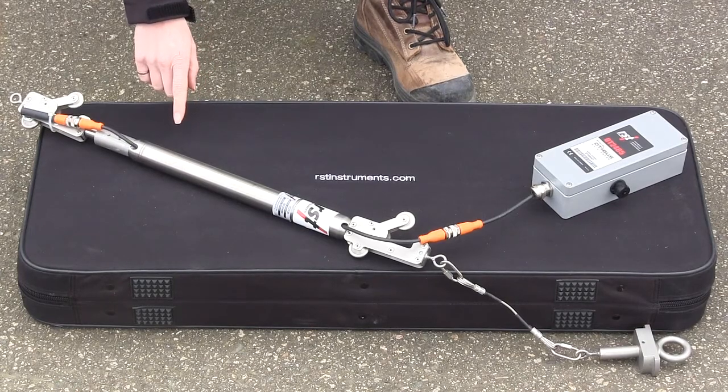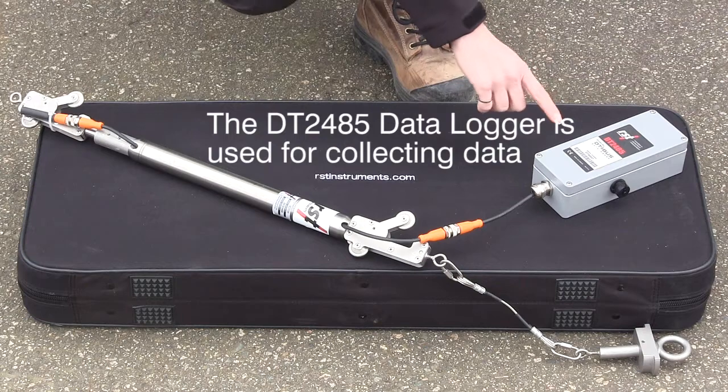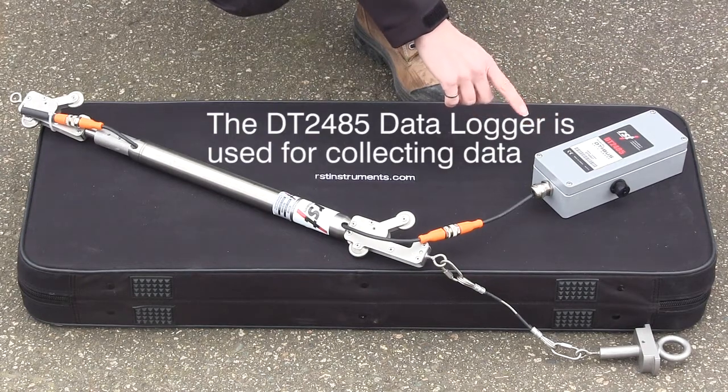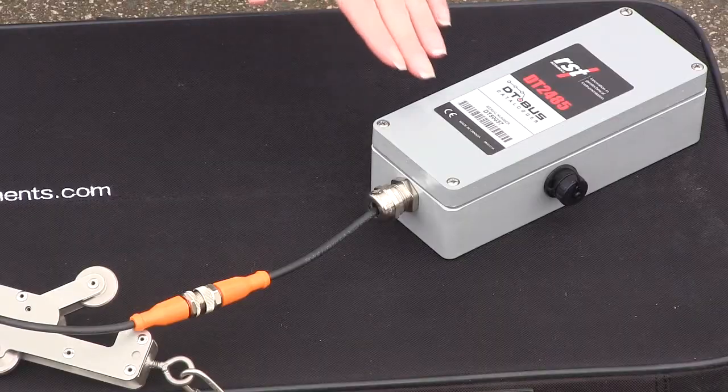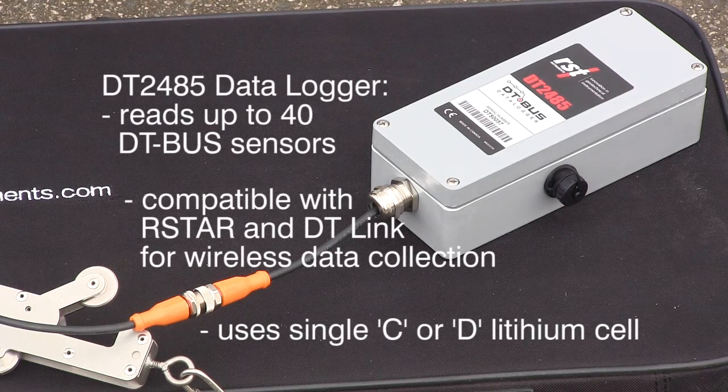IPIs can be connected to a data logger for automated data collection. This includes our DT2485 data logger or a FlexDAQ data logger. The DT2485 can read a string of up to 40 DT bus sensors. It is fully compatible with DT-Link and R-Star, and runs off a single C or D cell lithium battery.